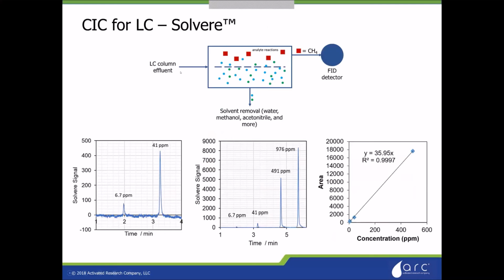In the same way that we convert all of our analytes to methane in GC, we are going to convert all LC analytes to methane for detection in an FID. So we're finally bringing FID to the LC community so that you can take advantage of that 7 order of magnitude linear range that is really unprecedented in LC. What happens here is our LC column comes in, and using a proprietary method I can't discuss too much today, we will remove the solvent, which can be water, methanol, acetonitrile, THF, a number of different solvents, completely and entirely. In so doing, we will also remove some of your analytes if they are volatile or similar in size to the solvents. So that's important to note. But the non-volatile molecules will be converted catalytically to methane so that we can detect them in the FID.